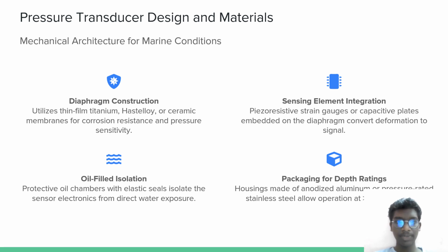Pressure transducer design and materials: mechanical architecture for marine conditions. Diaphragm construction: utilizes thin film titanium or ceramic membrane for corrosion resistance and pressure sensitivity. Sensing element integration: piezoresistive strain gauges or capacitive plates embedded on the diaphragm convert deformation to signal. Oil-filled isolation: a protective oil chamber with an elastic seal isolates the sensor electronics from direct water exposure. Packaging for depth rating: housing made of anodized aluminum or pressure-rated stainless steel allows operation smoothly.